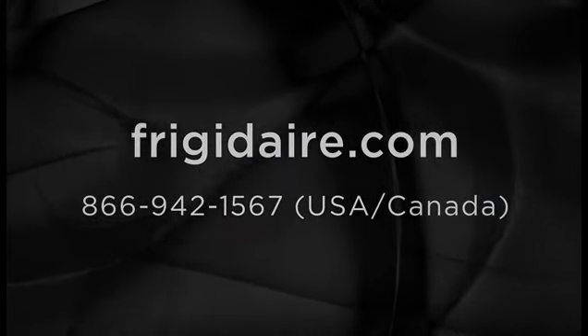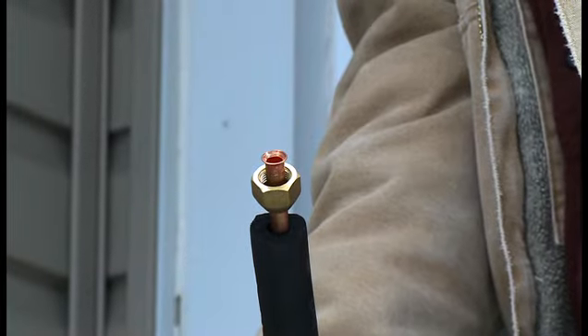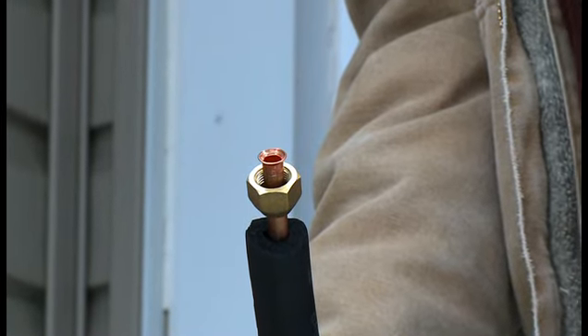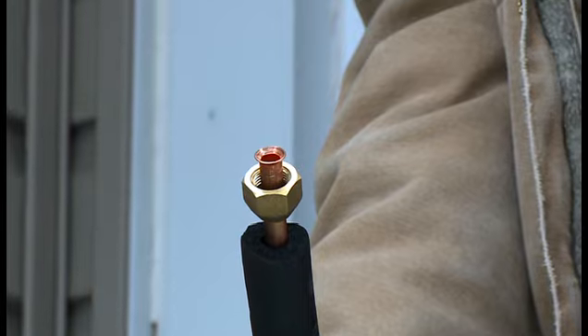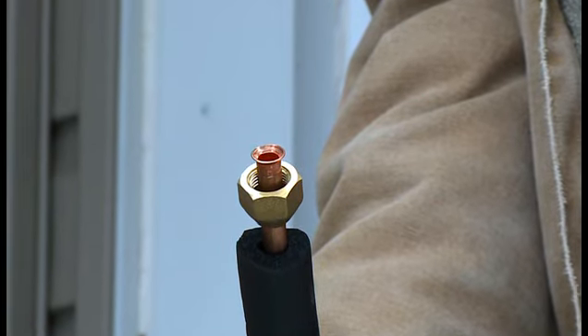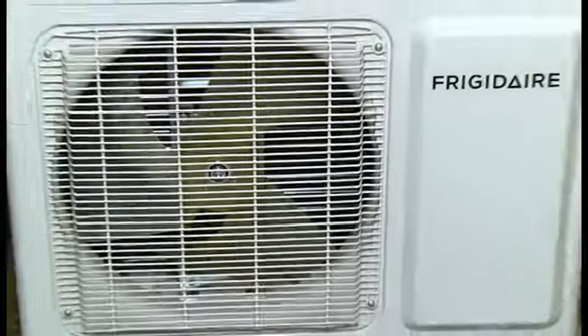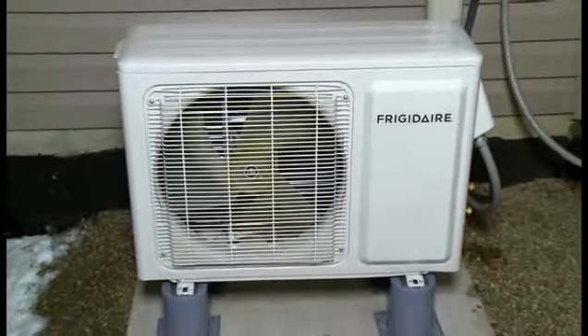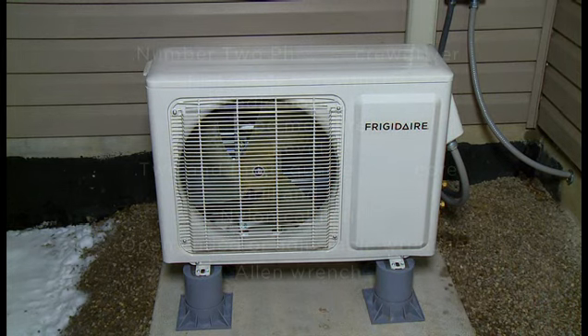Note in some models the refrigerant line set is included with the accessory kit. In other models, the line set is packaged with the condenser unit. The insulated copper line set tubes are factory flared and ready for installation. Also in this video, we are installing a 12,000 BTU air conditioner heat pump. Other models may be somewhat different.